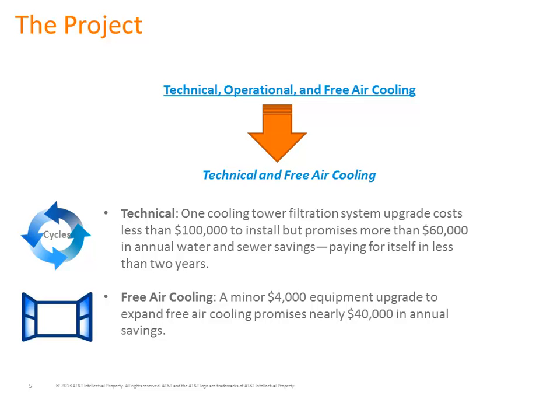We also found the greatest water and energy improvements—we're talking about water, but we can't ignore the energy side as we discuss the water and energy nexus—occurring when we reduced load on the chillers and towers by increasing our free air cooling. That takes advantage of outside air when it's cool, like opening your window when it's cold outside. This provides some or all of the cooling in a building, depending on the characteristics of the building and what kind of equipment it has.